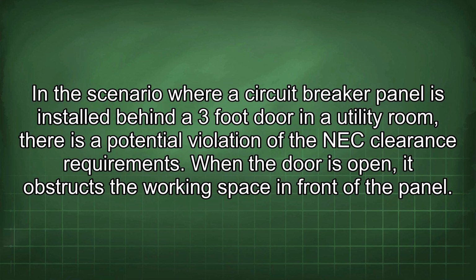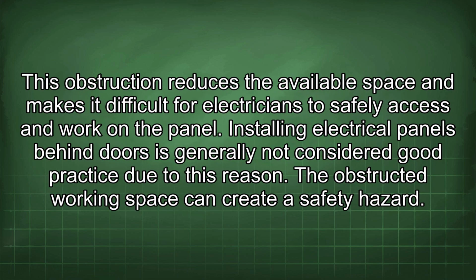In the scenario where a circuit breaker panel is installed behind a 3-foot door in a utility room, there is a potential violation of the NEC clearance requirements. When the door is open, it obstructs the working space in front of the panel. This obstruction reduces the available space and makes it difficult for electricians to safely access and work on the panel. Installing electrical panels behind doors is generally not considered good practice due to this reason.